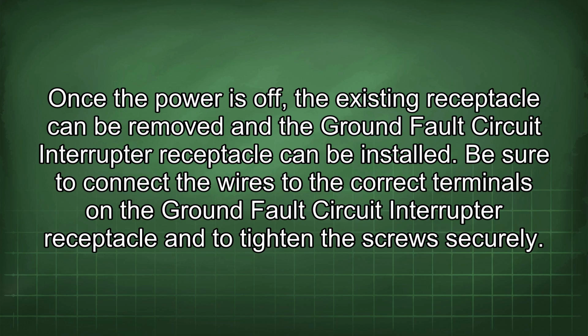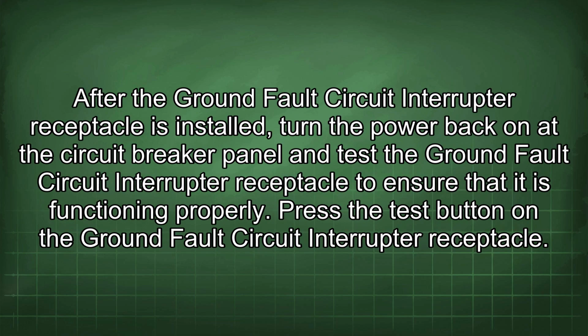Once the power is off, the existing receptacle can be removed and the ground fault circuit interrupter receptacle can be installed. Be sure to connect the wires to the correct terminals on the ground fault circuit interrupter receptacle and to tighten the screws securely. After it is installed, turn the power back on at the circuit breaker panel and test the receptacle to ensure that it is functioning properly.